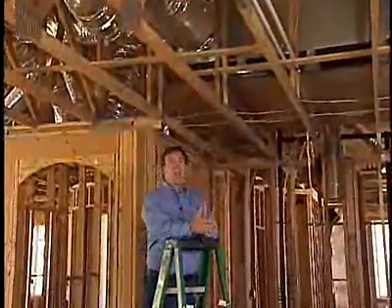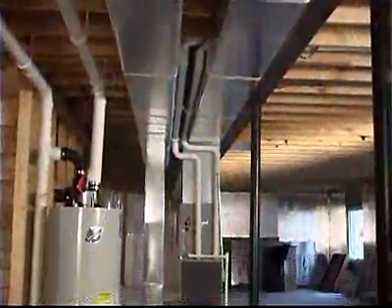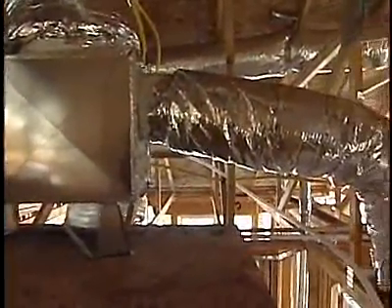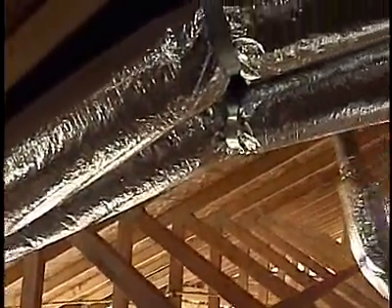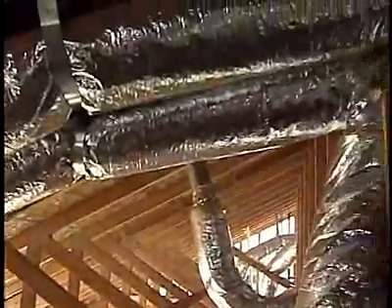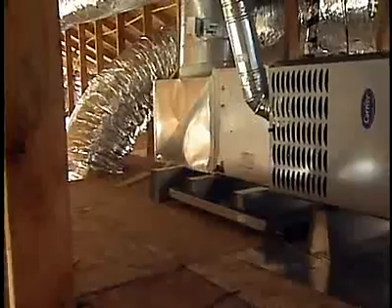Now, typically we see ductwork of two basic types. We see metal ductwork, which we call rigid ductwork, and then we also have flexible ductwork. Here what we're seeing are flex ducts, and basically it's kind of like a slinky. It's a helical spring-like wire that creates the ductwork, and then it has a plastic liner over that, and then we have our insulation, and then on top of that we have our reinforced foil. Now the metallized material over this insulation actually helps reject heat too. It reflects heat so the ducts don't absorb so much heat up in a hot attic.